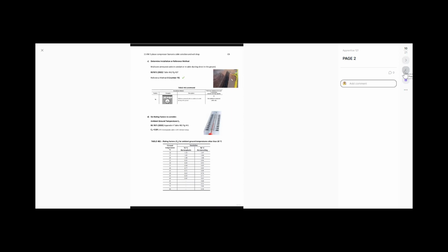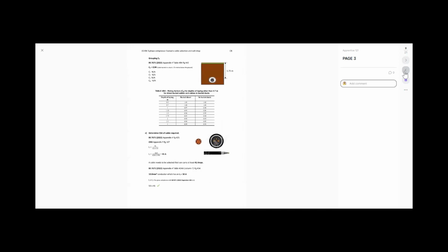So we've got to consider now what derating factors there are within our little scenario. So we know that we've got an ambient ground temperature of 35 degrees. That's the maximum we're expecting it to go. So we've got to find the right table again within Appendix 4 of the regs. Within Appendix 4, we can look at Table 4B2 on page 441, and that gives us rating factors for ambient ground temperature, not to be confused with Table 4B1, which we used last week, that was talking about ambient air temperature. We haven't got a factor for that one. We've only got a factor for the ground temperature because obviously the cable's going inside a duct in the ground. So we look down on the left, ground temperature, go down as far as 35 degrees. We come across, and we already know that the insulation on our multi-core armoured is 70 degrees. So the factor there is 0.84. Nice and simple. Happy with that? Yep. Excellent. And then we've also got to consider that the cable is buried.